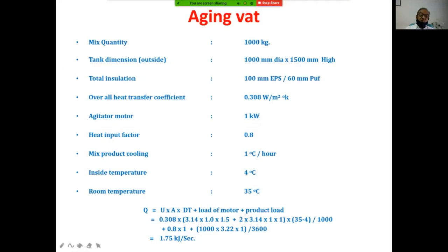So for the agitator motor, what is the load of the agitator, how much heat input by the agitator, everything is calculated here. You can see we have done the calculation for that. Inside temperature 4 degrees, room temperature 35 degrees, and mixed product cooling is 1 degree centigrade per hour. Assuming this, the UA delta T uses the standard overall heat transfer coefficient. The area of the tank is 3.1 for the periphery. Then there is the top and bottom area, multiplied by the temperature difference, room temperature minus tank temperature.